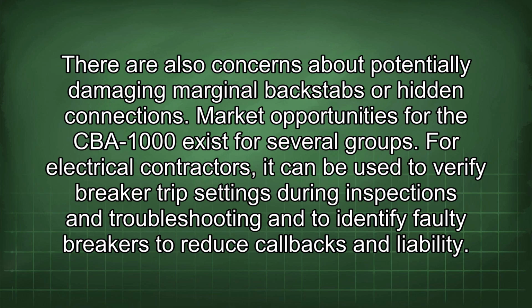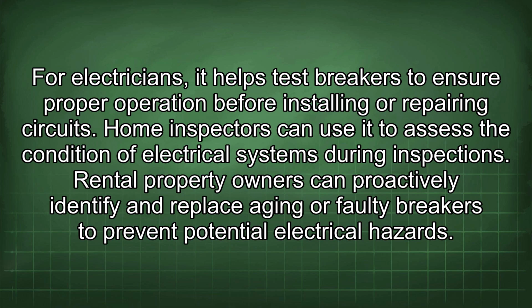Market opportunities for the CBA-1000 exist for several groups. For electrical contractors, it can be used to verify breaker trip settings during inspections and troubleshooting, and to identify faulty breakers to reduce callbacks and liability. For electricians, it helps test breakers to ensure proper operation before installing or repairing circuits. Home inspectors can use it to assess the condition of electrical systems during inspections. Rental property owners can proactively identify and replace aging or faulty breakers to prevent potential electrical hazards.